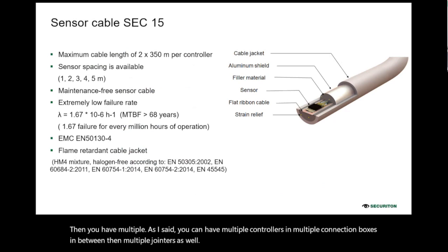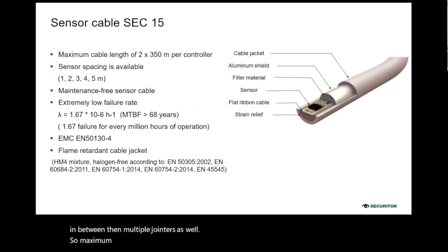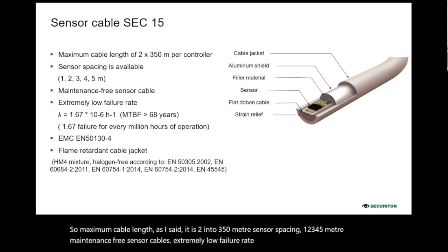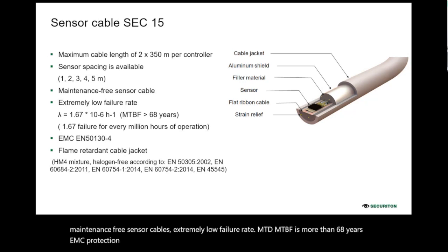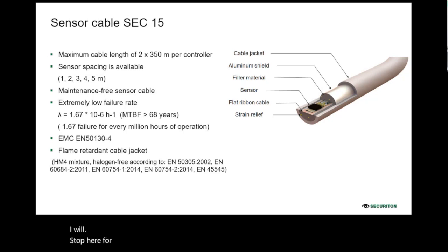So the maximum cable length, as I said, is 2 into 350 meter. Sensor spacing 1, 2, 3, 4, 5 meter. Maintenance-free sensor cables, extremely low failure rate. MTBF is more than 68 years. EMC protection is there, and these cables have flame retardant jackets. I will stop here for questions and answers. If you have a question, then we will take it.